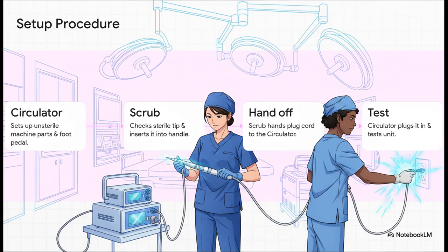Setting up equipment like that electrosurgical tool requires this highly choreographed dance to make sure the sterile field is never broken. It goes like this. The circulator, who is an unsterile team member, sets up the base machine and the foot pedal. Meanwhile, the scrub nurse, who is completely sterile, inspects the sterile surgical tip and inserts it into the handle. Then, the scrub nurse carefully holds the sterile end and hands the unsterile plug cord over to the circulator. The circulator plugs it into the wall and the unit is tested. At no point do the clean and unsterile worlds collide. It's just a flawless system of checks and balances.